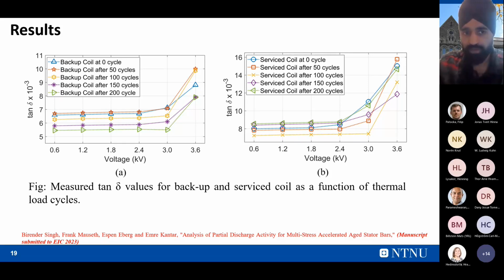Similarly, this kind of pattern we have observed: as the number of cycles increases, the tan delta values keep on decreasing. But at higher potential, the tan delta values are a little bit higher. If we compare this backup coil with the service coil, which is already in service, we found that its tan delta values are much higher for the 200 cycles. Its values are not decreasing as the number of cycles increases. At higher cycles, its tan delta keeps on increasing, this green color. So at higher potential also, we observe a higher value of tan delta.